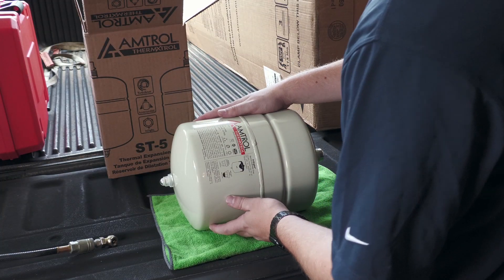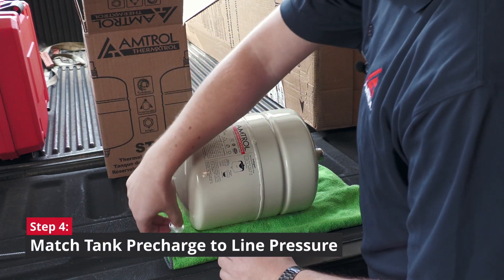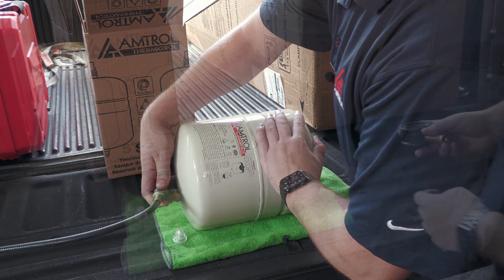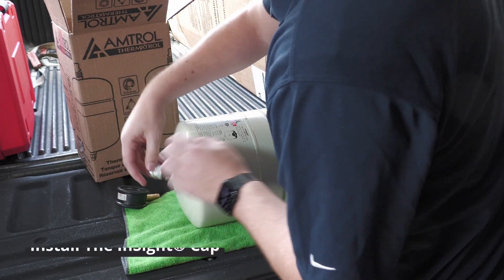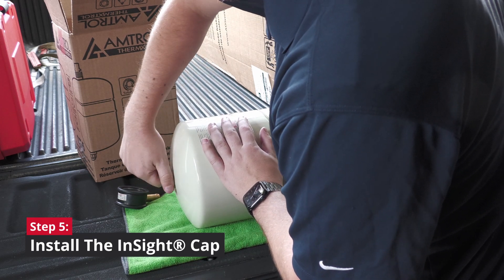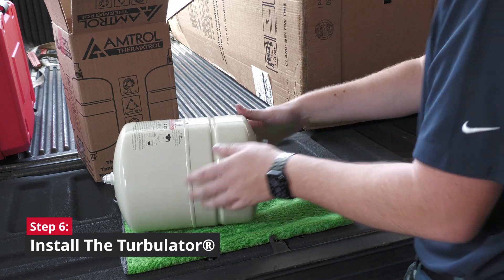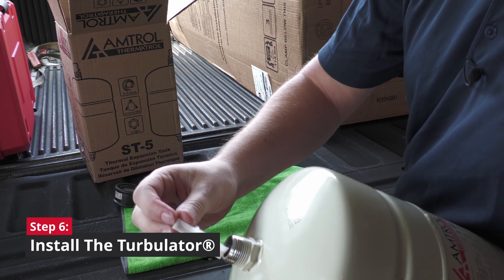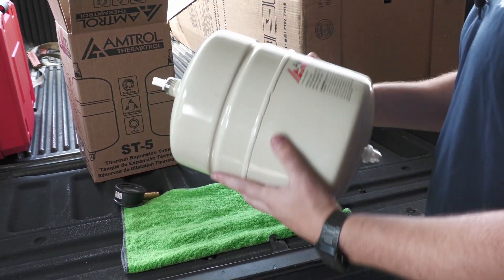Since we need to increase the pre-charge pressure of our expansion tank, the first thing I'm going to do is locate the air stem, which is right underneath the insight cap, and use a standard compressor to increase the pre-charge. We've increased our pre-charge right to 60 psi, which is perfect. I'm going to reinstall and tighten down the insight cap. I'm also going to grab the turbulator — our ST-5s come with a freshwater turbulator, so I'll install that right in the connector with the long end going in first, press it in, and now let's install this tank.